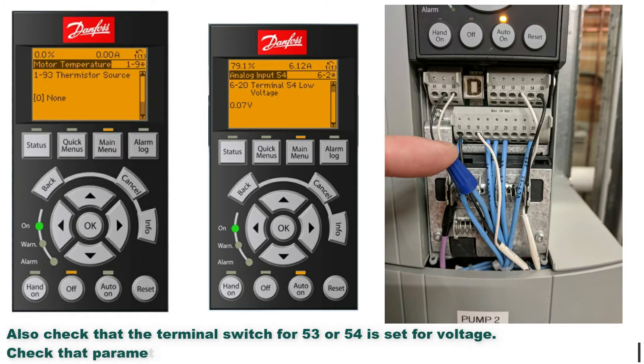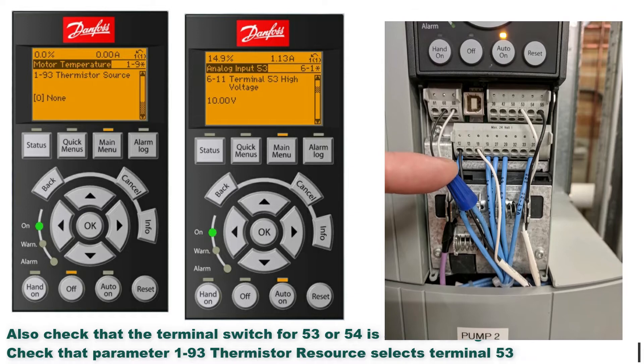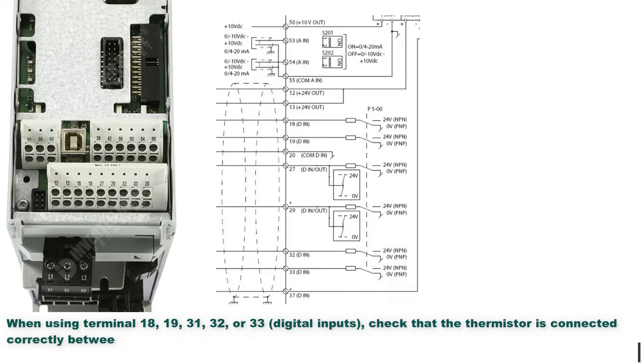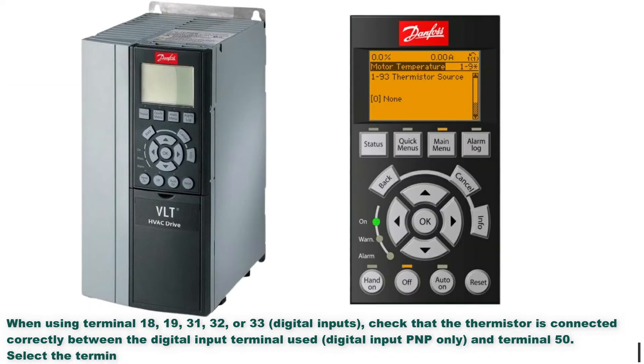Also check that the terminal switch for 53 or 54 is set for voltage. Check that parameter 193 thermistor resource selects terminal 53 or 54. When using terminal 18, 19, 31, 32, or 33, digital inputs, check that the thermistor is connected correctly between the digital input terminal used (digital input PNP only) and terminal 50. Select the terminal to use in parameter 193 thermistor resource.